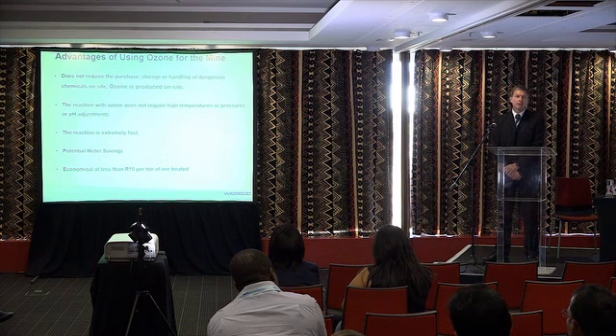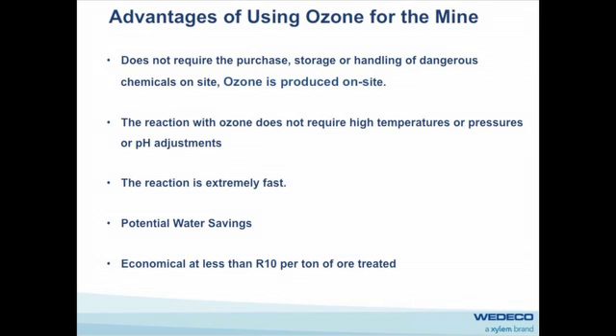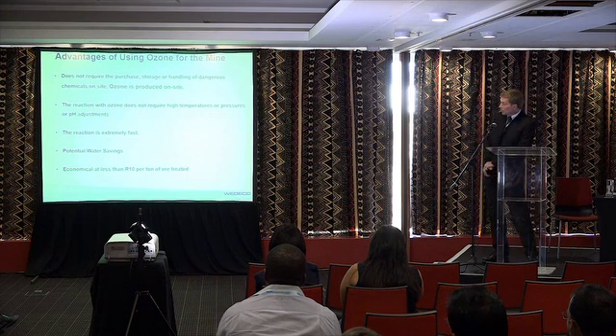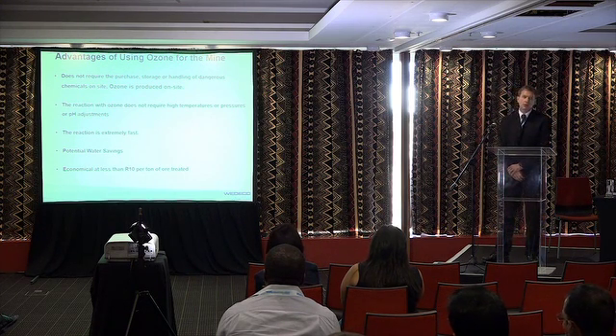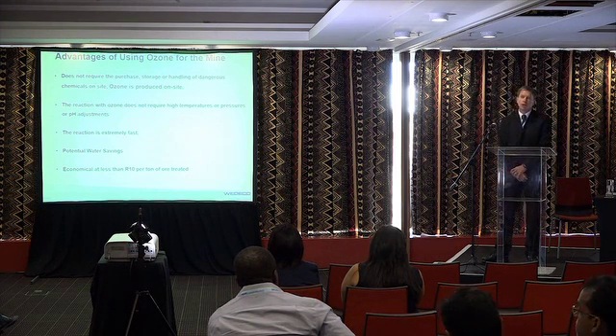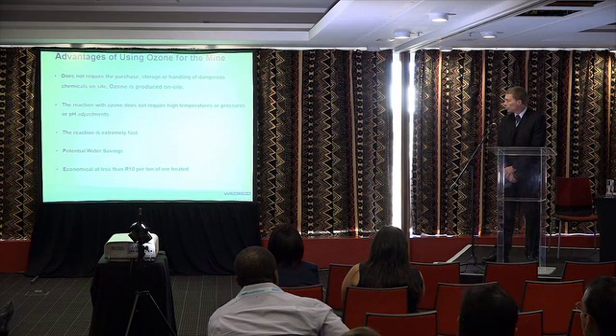Handling and dealing with hazardous chemicals on-site is increasingly a concern. With ozone you have a sealed container operating almost personnel-free on your site — no handling or moving of chemicals, no deliveries or unexpected costs associated with chemical storage. The reaction requires no change in process: you don't heat or cool solutions, don't change pH, and you can inject ozone directly into your tailings. There's also a potential water savings since you can recycle water back into your process without adding chemical loads. At this trial, the cost ran at less than 10 rand per ton of ore treated — quite an economical process.